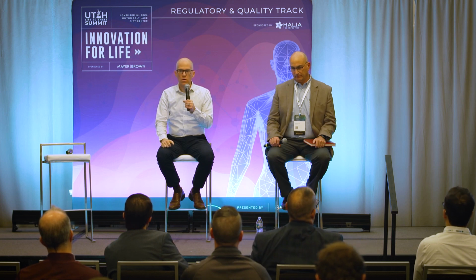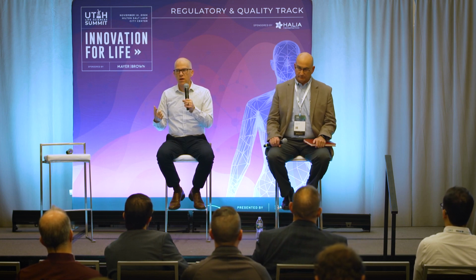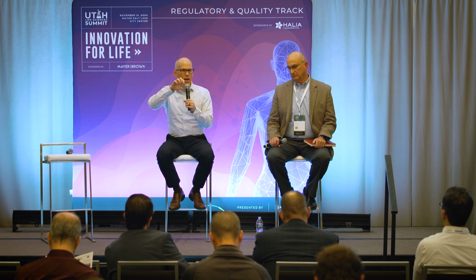risks. And then also, this is the important part, each vulnerability risk that we have identified could potentially have a safety risk as well. Like if somebody exploits this vulnerability and gets control of the system or does something, then it could have some association with our safety risk analysis. So I want to have some sort of process in place where I take every single cybersecurity risk and reanalyze it against our safety risk analysis to see how it connects, if it does. Okay, next slide.